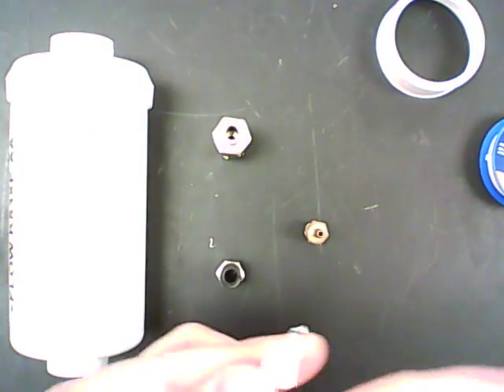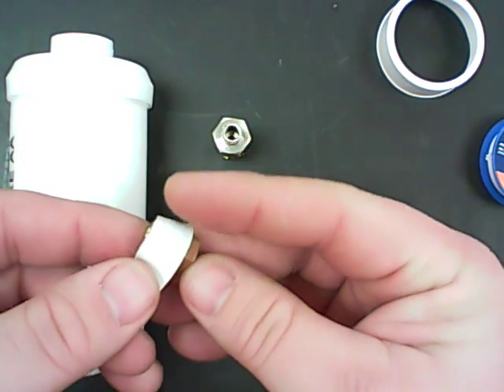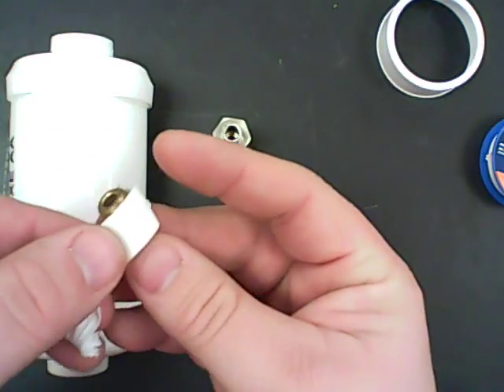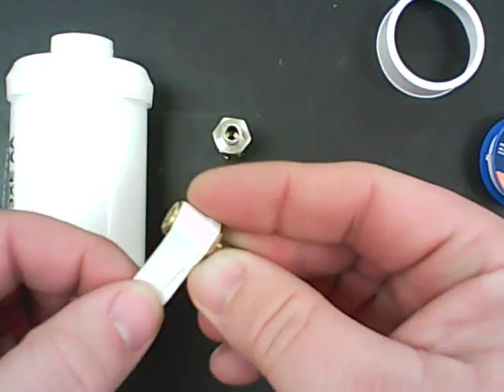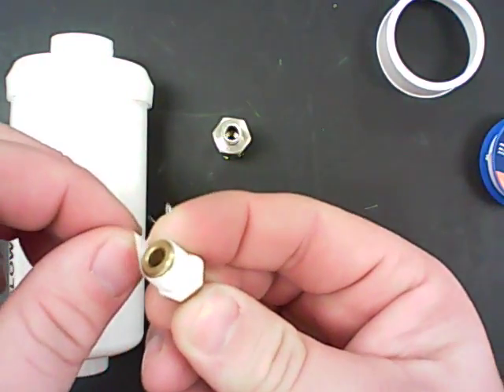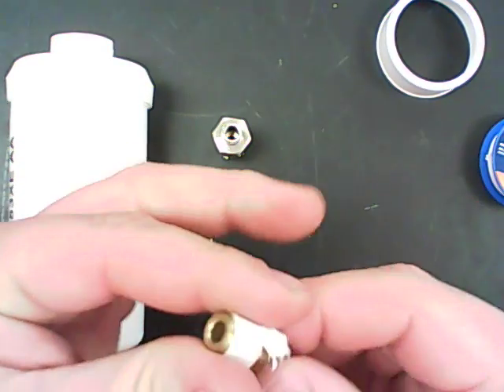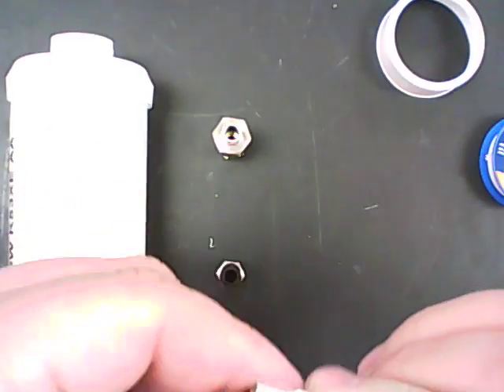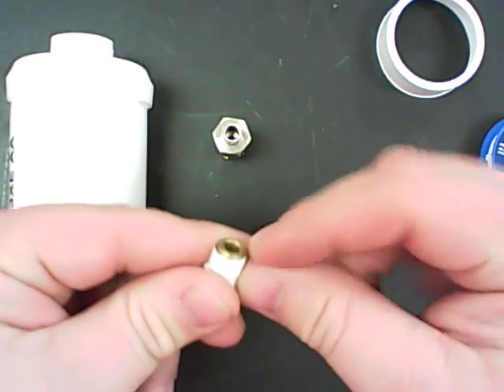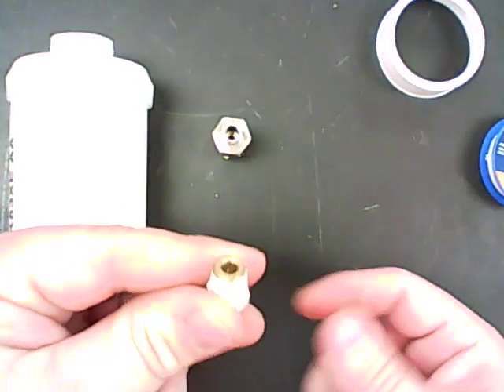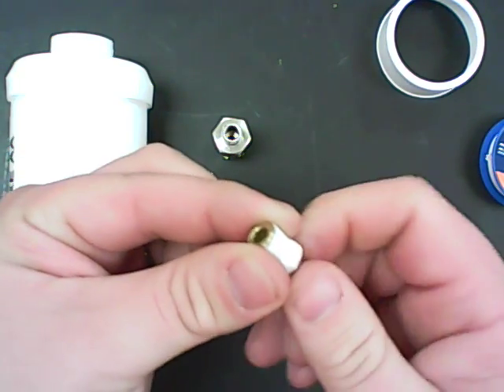I'm going to take my male connector here first and I am going to just lightly lay it across. I am going to line it up so that my tape goes over the threads as you see here. But I'm not going past the actual mouth or the opening where the air gets pushed into. The reason being is because as my air is getting pushed into this, if I have tape here, it's going to restrict the air flow and it won't actually allow me to go in. So I now kind of tighten this tape around here with my finger.